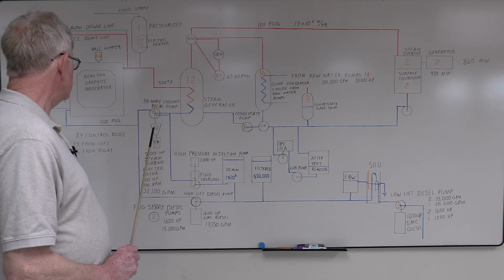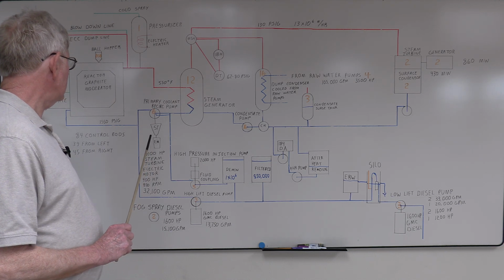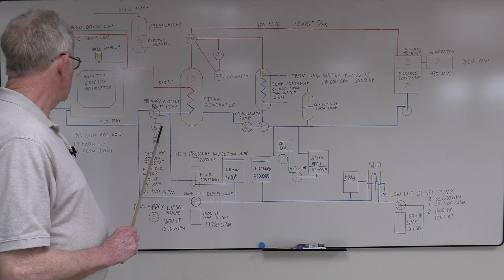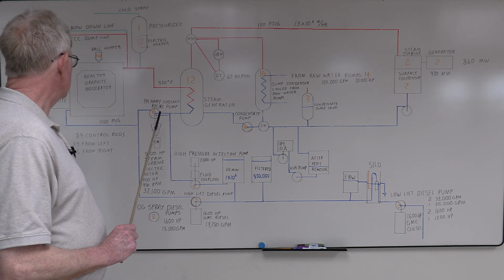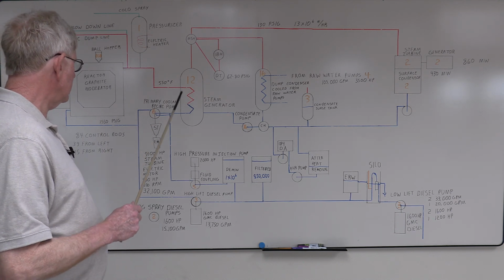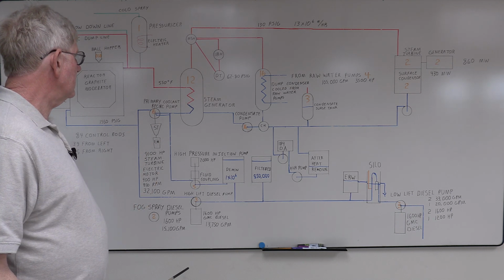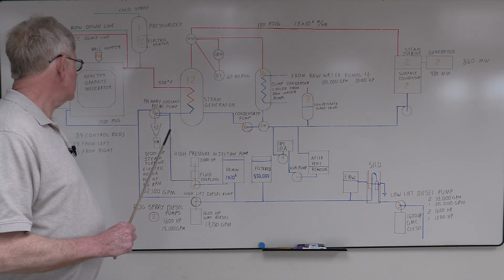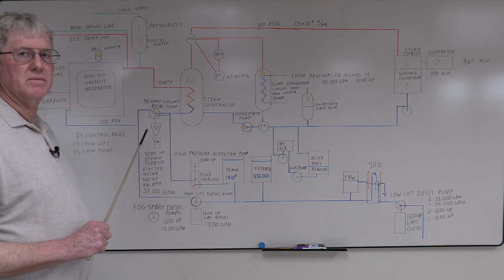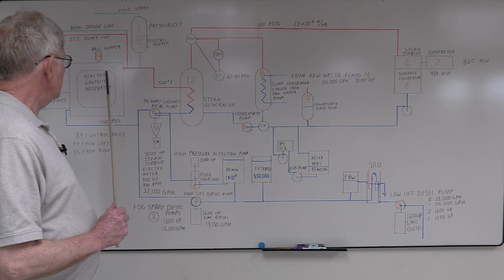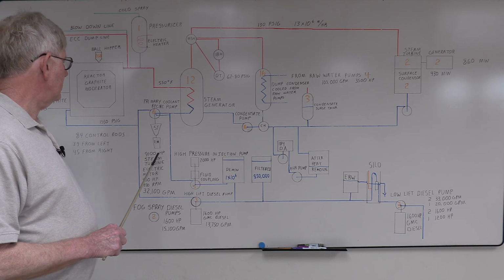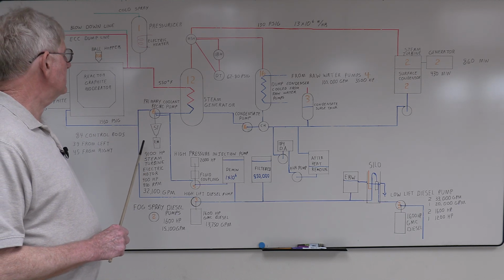Your primary coolant pumps, steam turbine drive, went down to 1,100 RPM when the reactor scrammed to minimize excess cooling in the loop. Plant startup, the boilers were capable of driving these steam turbines to about 1,700 RPM. After that, you'd have to produce reactor steam to drive them up to the 3,600 RPM where they ran.